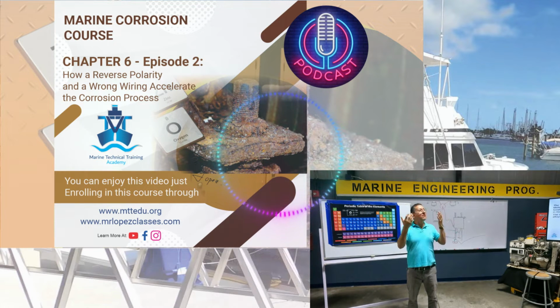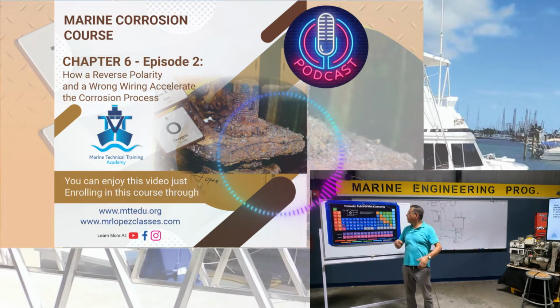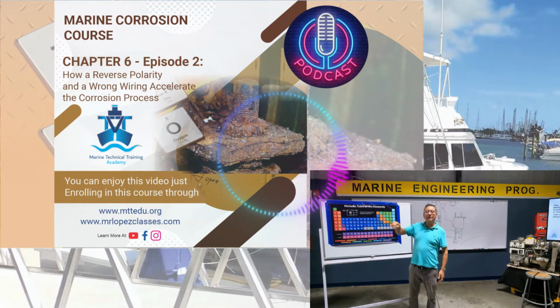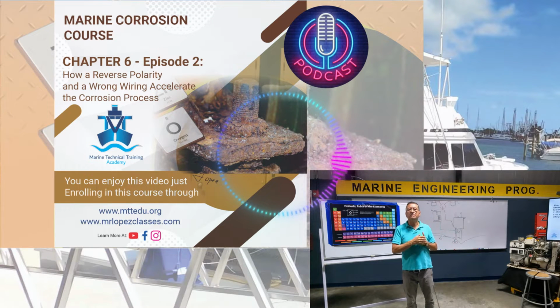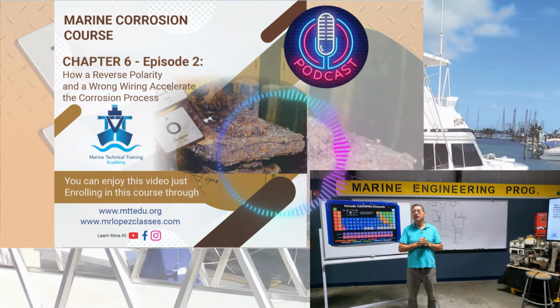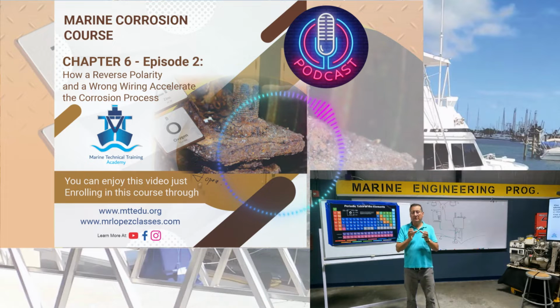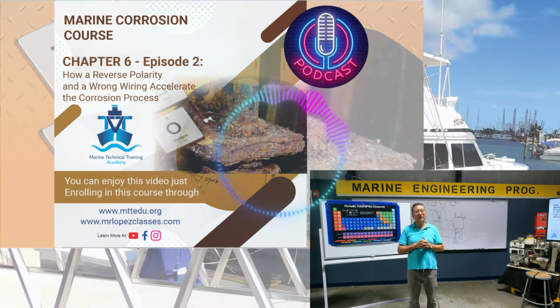All right, my friends, important. The galvanic isolator is the first element to protect my boat from the neighbor boats. Because if the neighbor boats have leaks of current, when those leaks try to enter, my galvanic isolator protects. And also, if the ground of the marina, the ground of the building, is not good, the excessive current flowing through the ground does not enter my boat. Remember, through the ground, normally the current should be zero.